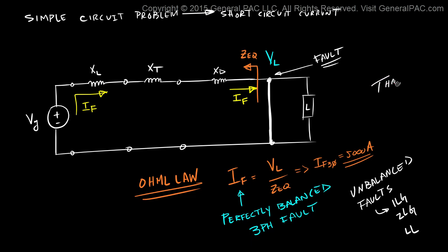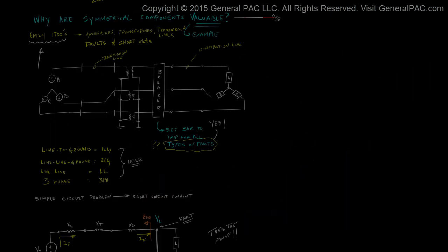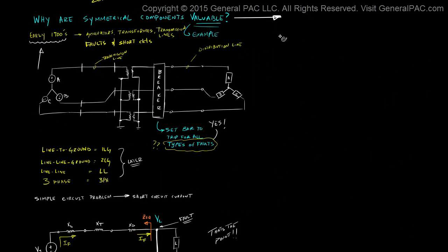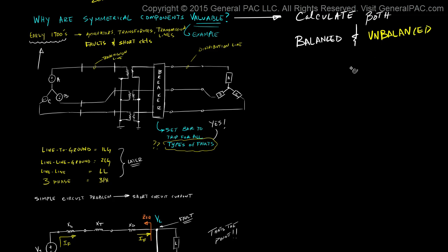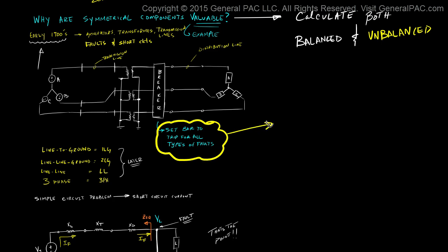And that is the defining point. Without symmetrical components, we can only calculate balanced three-phase fault types. Without symmetrical components, it would be extremely difficult to even attempt to calculate unbalanced faults like the line-to-ground, two-line-to-ground, and line-to-line fault types. So what is the value of symmetrical components? With it, we can easily calculate both balanced and unbalanced faults, and we are able to properly set the breaker for all expected fault types on our distribution line. And that is extremely critical for the reliability, security, and integrity of the power system.